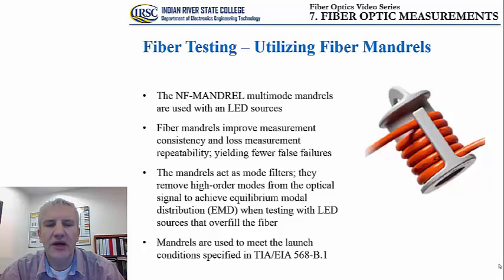As an implication of the use of fiber mandrels, they improve measurement consistency and loss measurement repeatability, because that ultimately yields fewer false failures, and that's why use of this accessory is desirable. And as I said, this accessory is an important standard accessory in any kind of OLTS or OTDR.